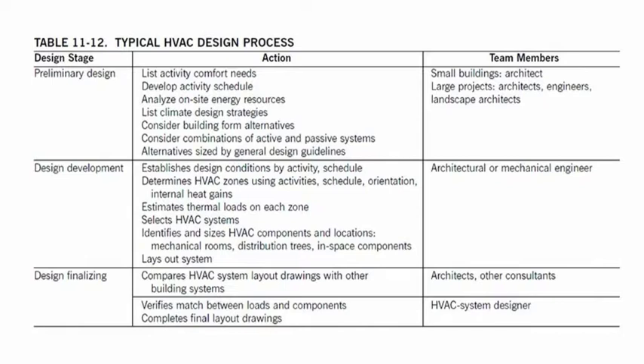Actions in this stage include establishing design conditions by activity and schedule, determining HVAC zones using activities, schedule, orientation, and internal heat gains, estimating thermal loads on each zone, selecting HVAC systems, identifying and sizing HVAC components and locations — mechanical rooms, distribution trees, in-space components — and laying out the system.